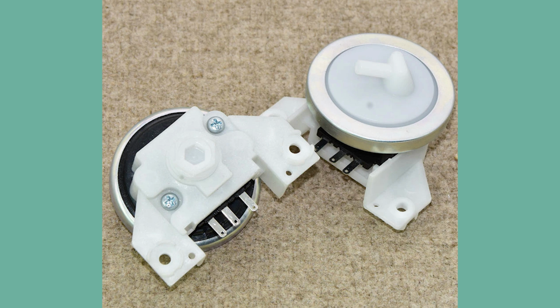If that doesn't work, you need to check the pressure switch and its connected air hose. Look for kinks in the small air tube, debris or soap buildup clogging the tube, and loose connections at either end. The pressure switch is usually behind the control panel. Find the small clear tube connected to it and disconnect it. Try blowing through it gently to clear any blockages. Don't forget to check the drain trap while you're at it. A clogged trap can cause pressure problems in the system. If you've tried all this and still get the error, you'll probably need to replace the pressure switch itself. It's about a $20 part and takes about 30 minutes to swap out if you're comfortable working with basic tools.